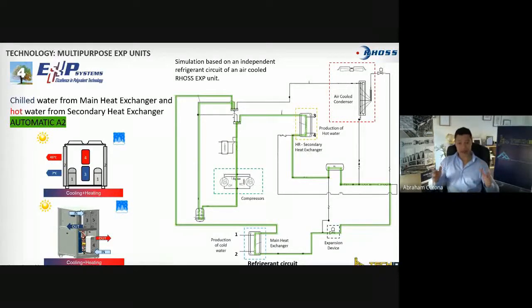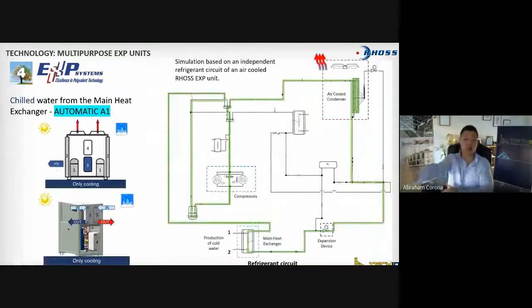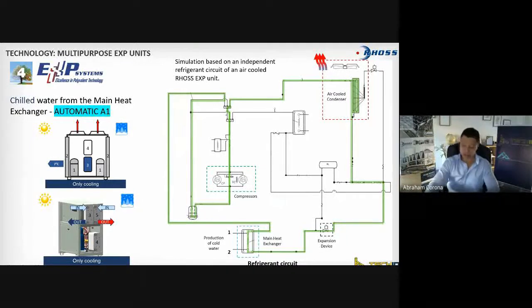So by itself, the unit recognizes the requirement of heating and cooling. Let's say that you comply and you satisfy that demand of heating, and when you satisfy that demand, I don't need to heat anymore. The unit by itself will say, I don't need heat, and in that moment, that four-way valve will redirect that heat again into the air-cooled condenser. Basically, we go back into the chiller demand.